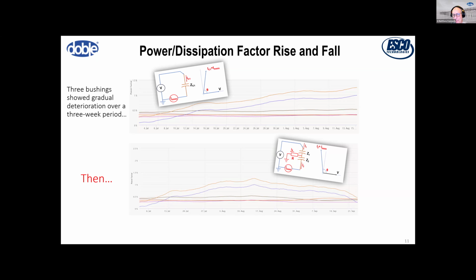At a higher level, what's occurring is that there's a lot of leakage. If you get enough leakage going to the ground flange of that bushing, or inside that cap adapter, so much that it starts to overpower the measured signal, you'll essentially start bending your reference angle, which makes the power factor go low, if not negative.